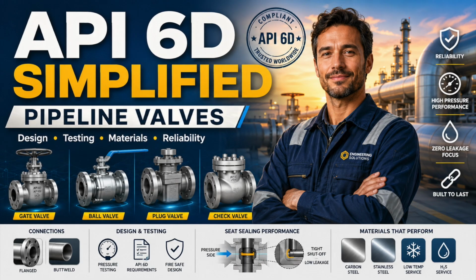A valve can leave the factory after passing all tests and still begin degrading because it was not properly drained, dried, lubricated, and preserved. Storage can undo good manufacturing just as easily. Flange faces need protection. Weld ends need protection. Internal surfaces need preservation. Actuators need weather protection. Valves must be lifted from approved points. They should not be dragged, forced, or stored carelessly. A valve can be damaged before it ever sees process pressure.